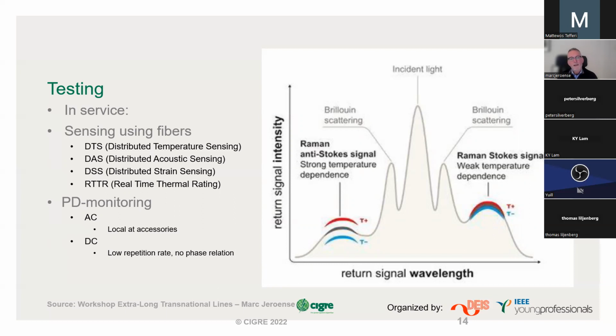One can use the sensitivity of these fibers to temperature and strain to detect the temperature in a distributed manner along the cable, and even to listen via acoustic sensing to what is happening along the cable, which is very useful when there's a failure. You want to detect the fault, since the breakdown will make sound, so you can listen at the end of one fiber and locate where the error is.